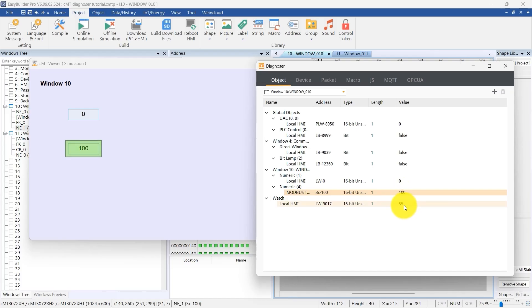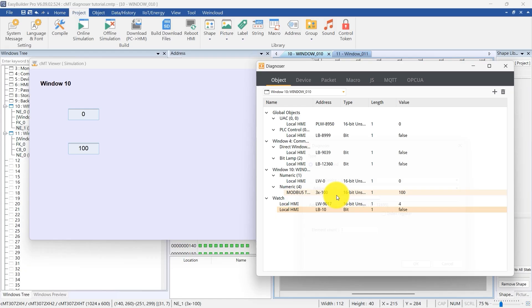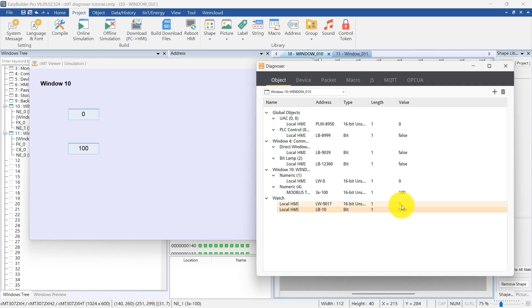The watch function in CMT Diagnoser allows us to monitor variable values in real-time. LB10 will be added and set to ON, demonstrating the ability to read and write values. This is particularly useful for monitoring addresses not displayed on the HMI screen.